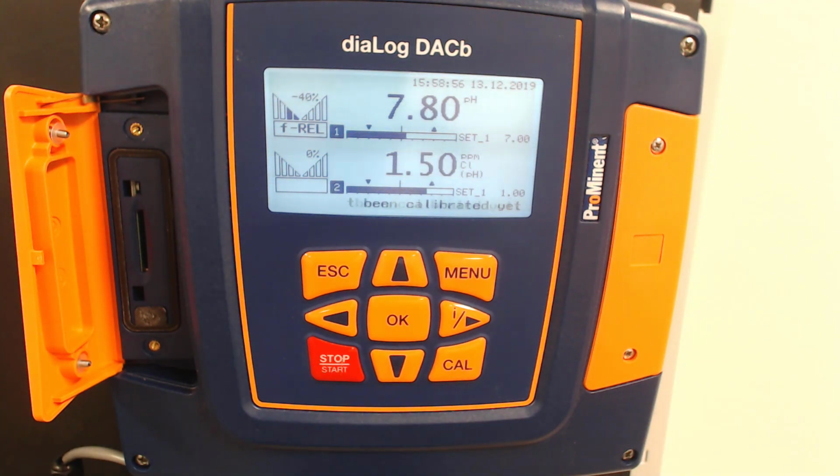It is still logging data while the card is out. While that card's out, it's going to store that data to an internal memory. If we have it set up to log every 10 seconds, it will be able to log for a day before that internal memory is filled up. If we have it set up for 60 seconds, for example, it will give us 6 times that. So it will be somewhere around 6 days of data before it's going to have to start writing over that in the internal memory.